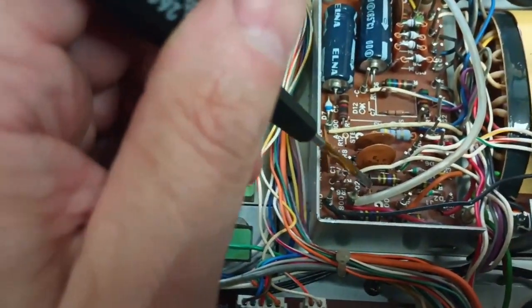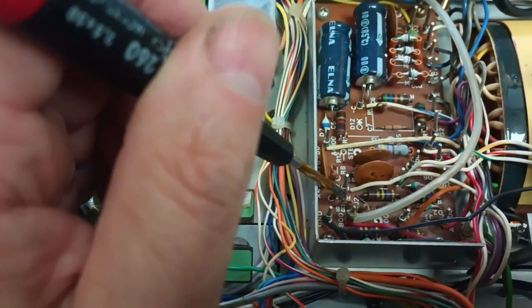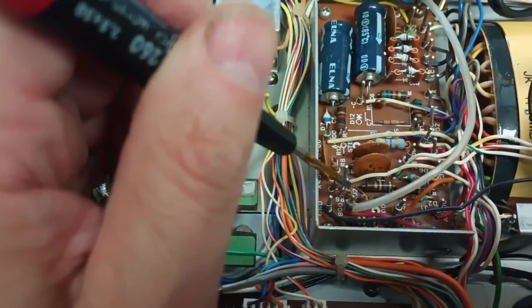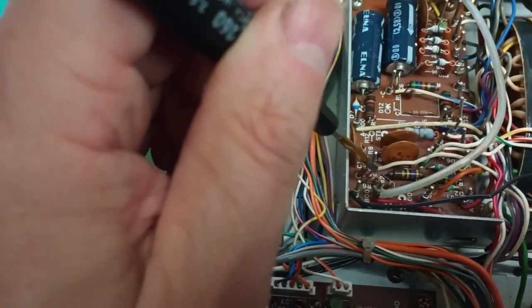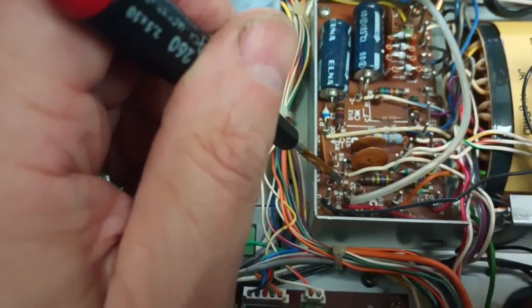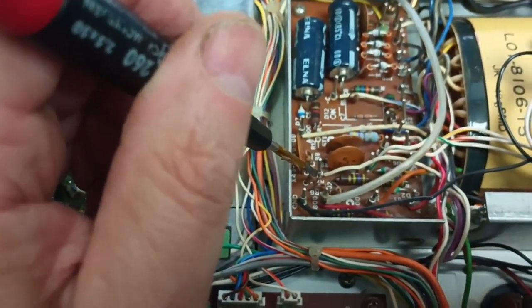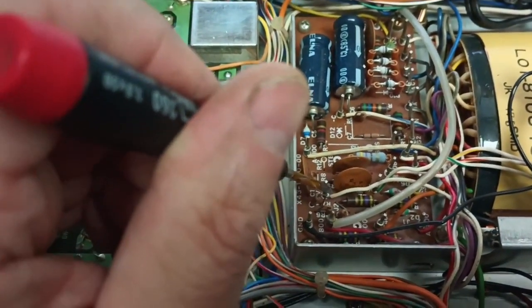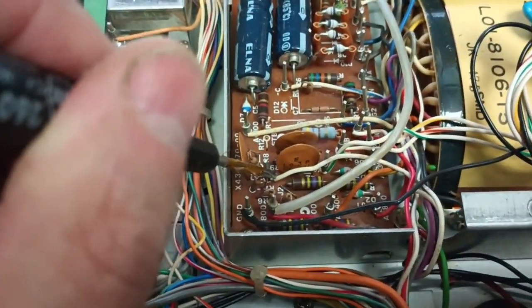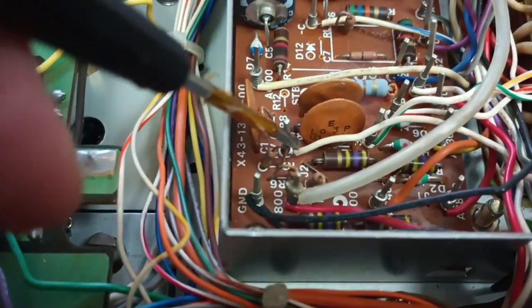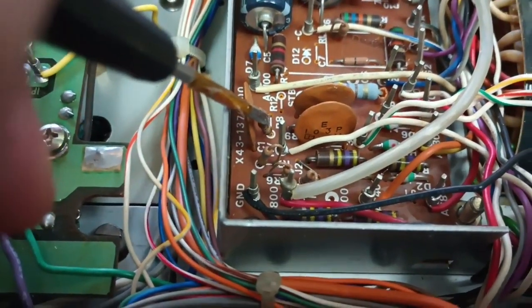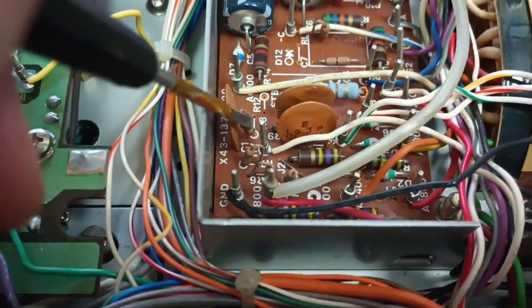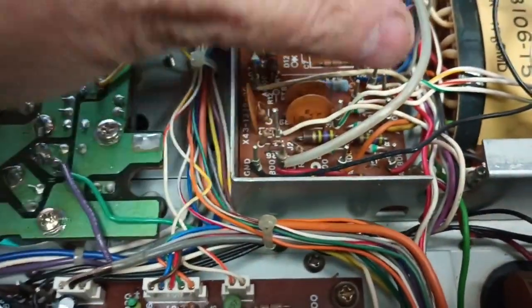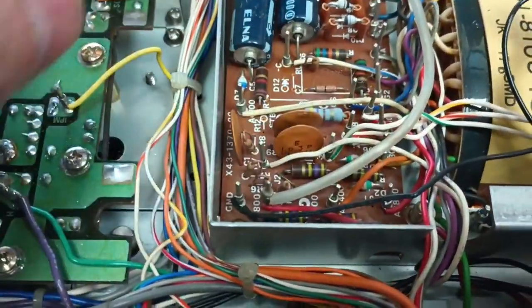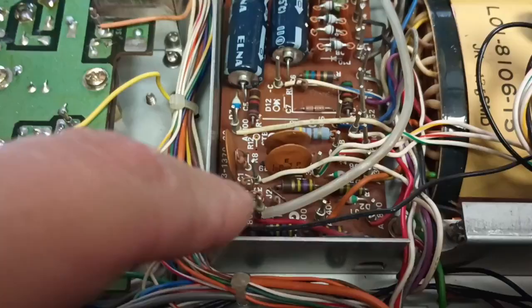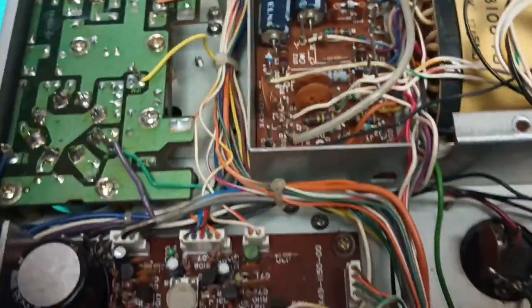And for the high voltage meter, R5, 6, and 7 are 680K low voltage resistors. Those equal 2 meg. That's no good. They've changed value, so the plate voltage meter is reading 950, which is too high. Those go to the plate meter terminal here at HV, right there, and then to ground by 100K ohm, just an ordinary, that's fine. That's low voltage at that point. So everything from here on over is operating at not quite a kV, and there's no excuse for stuffing all that on the end of that board.